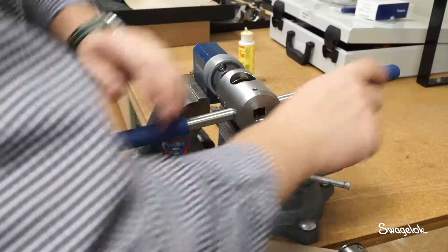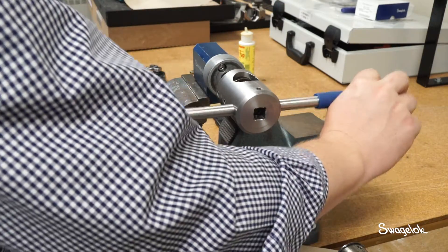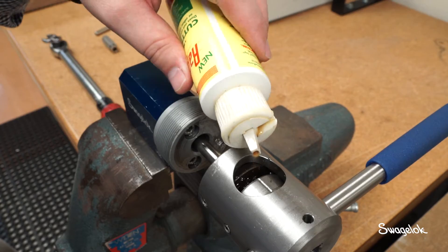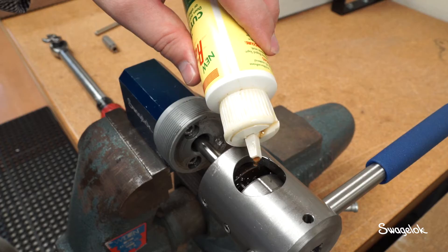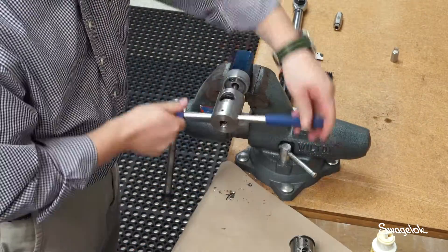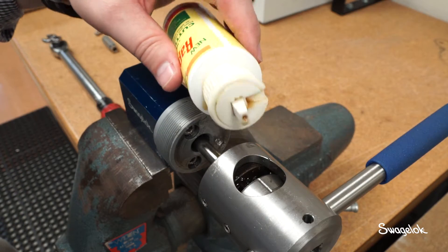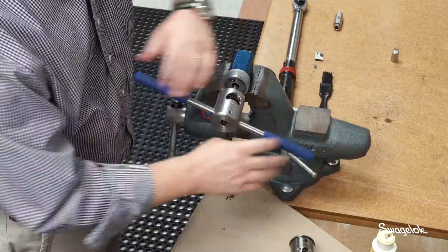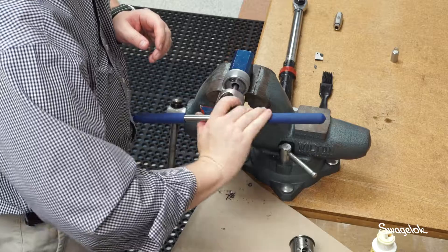Advance the threading tool clockwise one more full turn. Reverse direction one quarter to one half turn to break chips, then apply cutting fluid to the threading die. Repeat the previous step, adding cutting fluid every other turn while counting the number of turns until the proper thread length is reached, so that chips are broken every revolution and cutting fluid is added every two revolutions. Depending on the tube size and connection type, the required number of revolutions to achieve the proper thread length will vary.